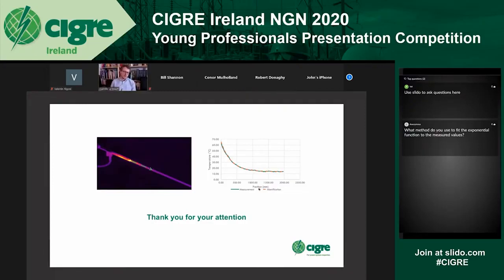Oh, no, way more significant than that. Especially because usually when you do your measurements, the wind is not that big, and you want to extrapolate the measurement to a super small wind with a lot of intensity to get the highest temperatures a joint could get. If you make a small error there, it has a huge impact on the final measurement you want to get to assess the risk of failure.